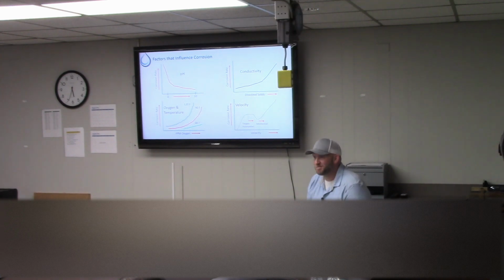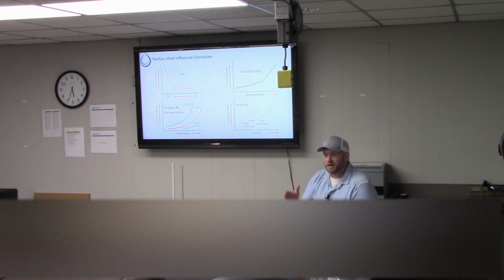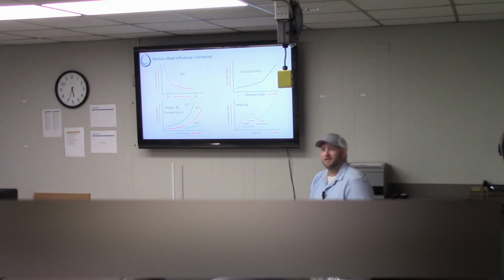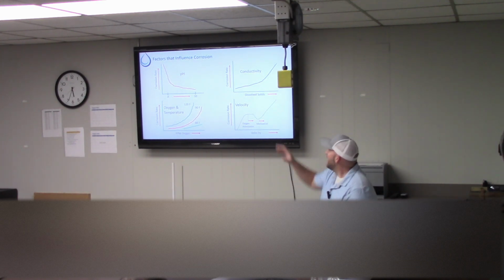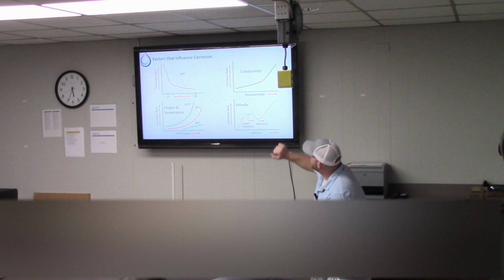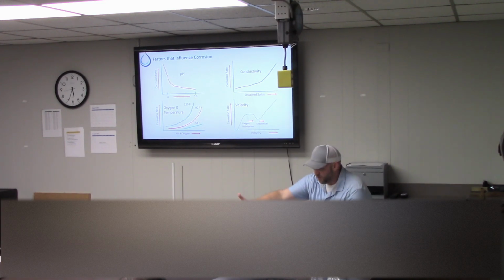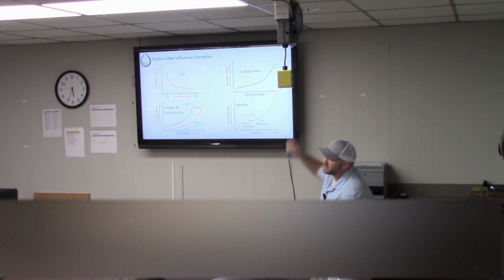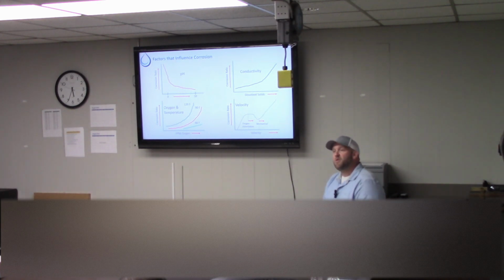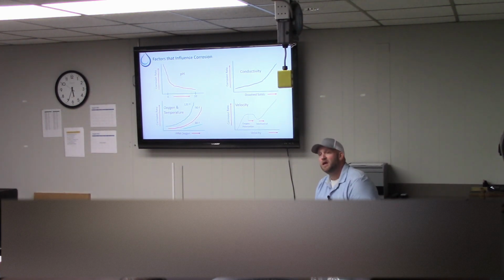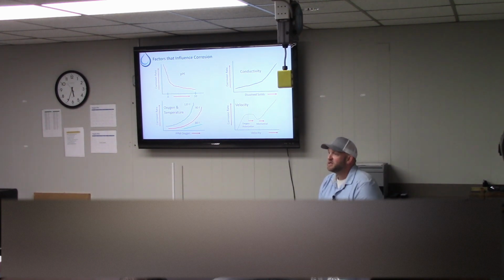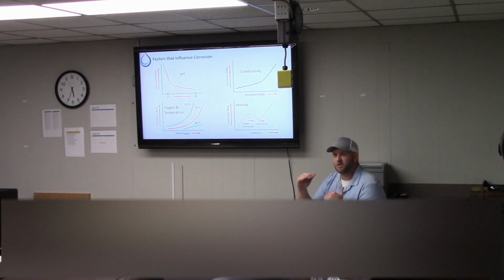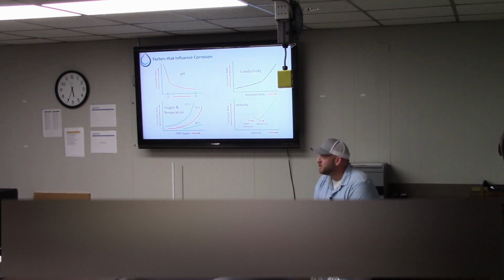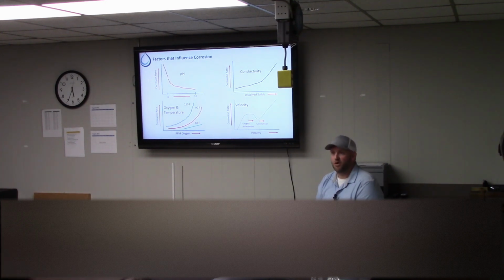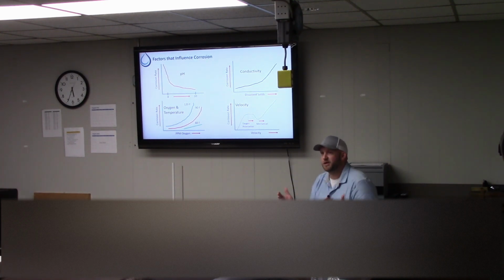You will not kill your spouse for the insurance money. But if you put some salt in the water, it'll go there. You'll get higher conductance, which means for metal you can increase the corrosion potential, which is why we utilize conductivity as one of our most common metrics, to make sure we don't exceed a certain value—because bad things start to happen, not only to the metallurgy but also to things like deposition and corrosion, which again are all interconnected.